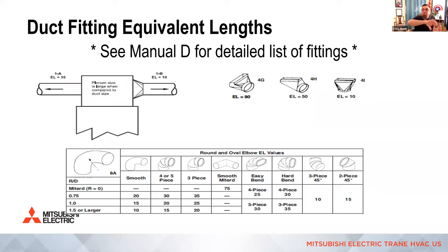So when it's smooth and a long radius, we could have as small as a 10-foot fitting. But typically we're working with 30 or 35 foot 90s because that's what people buy. It's the cheapest and that's what distributors stock. So if we're talking about low static air handlers, we want to use smooth, long sweep 90s. If we're talking about high static handlers, they can overcome that. You can use those.